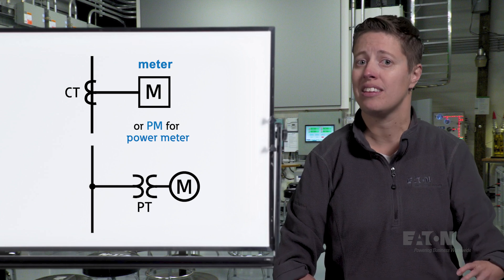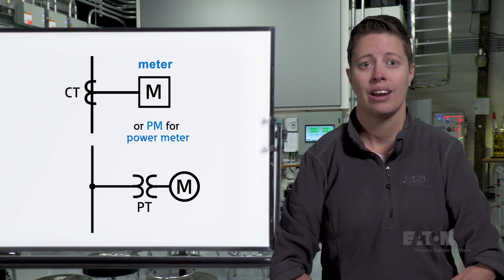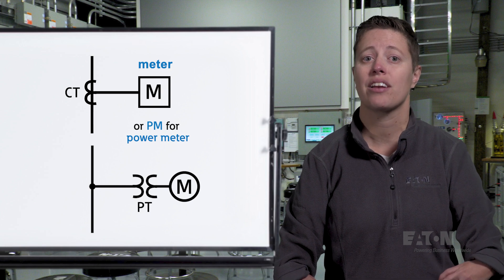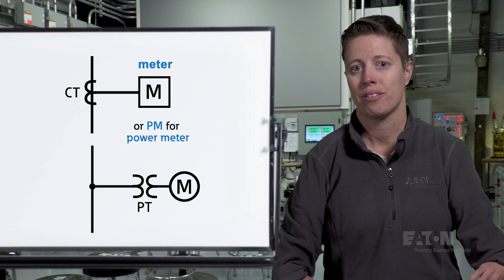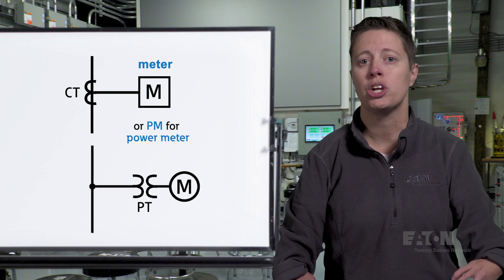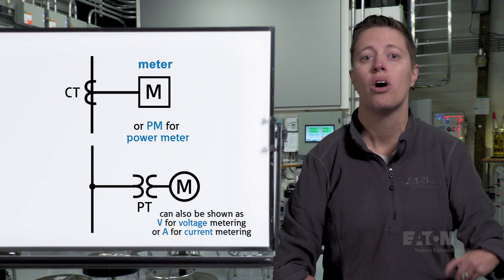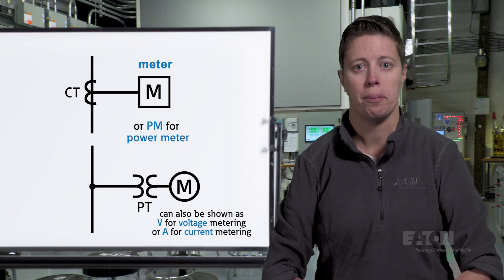We need to be careful here as we already discussed an encircled M in context of a motor load. If the M is fed from CTs, it is a power meter. If the M is directly connected to the load side of distribution equipment, it is likely a motor. A meter may also be shown as a V indicating voltage metering or an A indicating current metering.